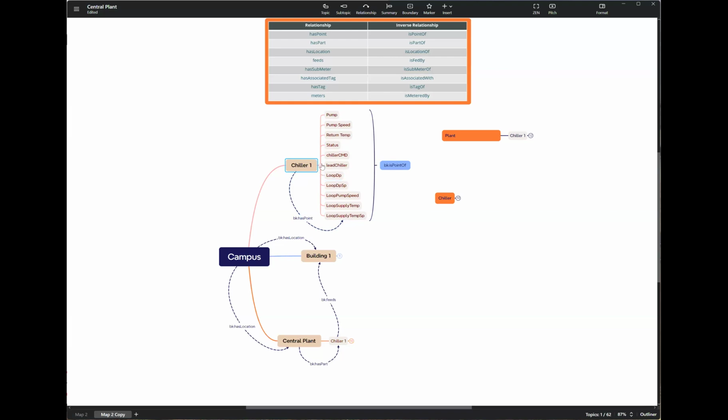We're going to then get into a little more detailed one where I create a bunch of folders just to walk through this. But let's say I have a campus, and this is a supervisor, and this is going to show you some of the power of how it's almost like a map of how to get to one point, and anywhere in the map I can figure out how to get back to the beginning. With the campus, I've got some relations that talk about that, here's a building and here's a plant. Those are usually separate. So I'm going to use the relationship that this has a location. Campus has a location and it's building one, and it has another location called the plant, the central plant. That's going to allow me to find the campus and then find all the buildings. And then once I get to a building, I can do several things. I'm going to stick with using has a part, but I have an example up here which I'll walk through to explain. And you can do multiple. I've actually got it both, but I'll show you again.